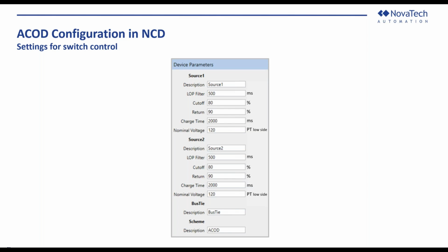For the return, it's looking for at least 90% of the nominal voltage to return before it considers it a return of potential, again for that 500 millisecond window, before it recognizes it and will operate on that. Then we have the charge time set for 2000 milliseconds in this example.